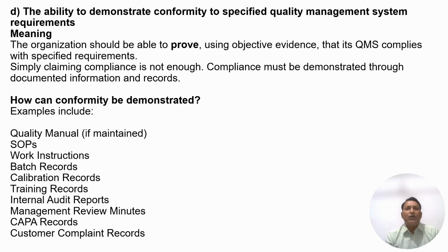The ability to demonstrate conformity to specified quality management system requirements. What is the meaning of that? The organization should be able to prove, using objective evidence, that its QMS complies with the specified requirements. Simply claiming compliance is not enough. Compliance must be demonstrated through documented information and records. How can conformity be demonstrated? Examples: quality manual if maintained, SOPs, work instructions, batch records, calibration records, training records, internal audit reports, management review minutes, corrective and preventive action records, customer complaint records, etc.